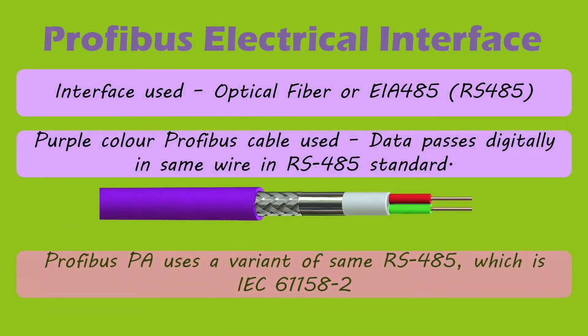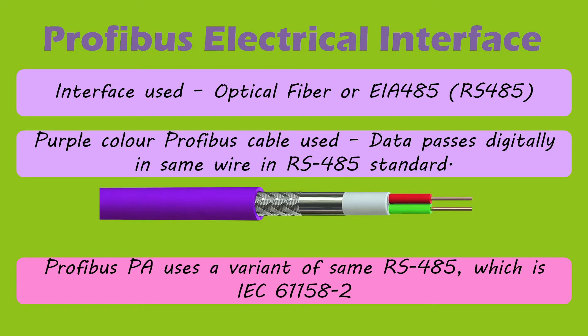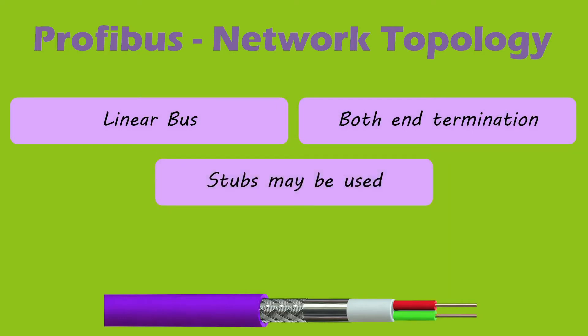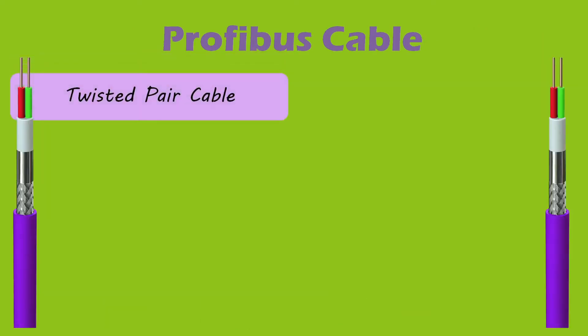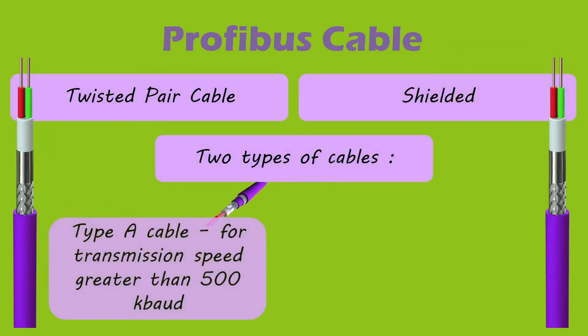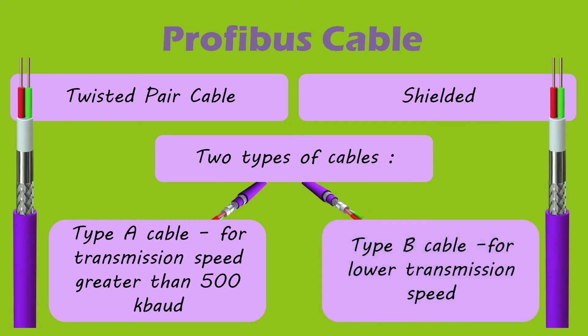Regarding the Profibus electrical interface: Profibus uses fiber optic or EIA-485, also known as RS-485, as its electrical interface. Normally, a purple colored wire is seen in use in Profibus networks, passing information through digital communication using the RS-485 standard. Profibus PA uses a variant called IEC 61158-2 for its electrical interface. The network topology used in Profibus is a linear bus terminated at both ends, with stubs — branch lines from the main line — used in some applications.